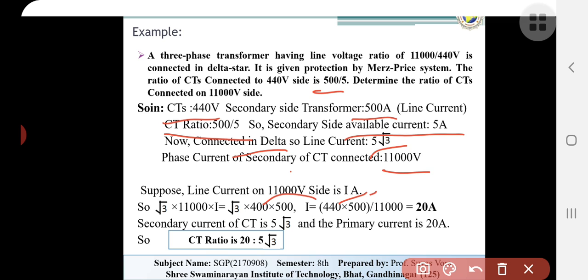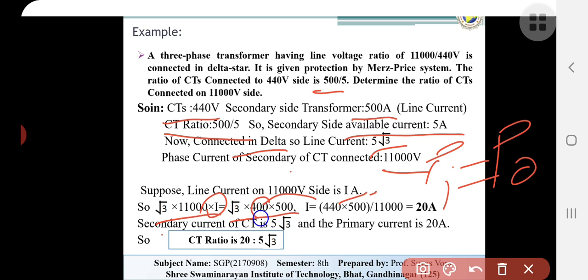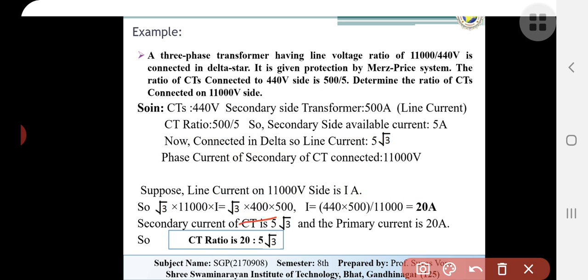So basically we equate the primary and secondary sides, because we know that the input power is equal to the output power. So here you can see √3 VI. Here V is 11,000 and I we can find from √3 × 440 × 500. Sorry, there is an error here, it should be 440, my mistake. So I is equal to 440 × 500 divided by 11,000, so 20 amperes. So we can see that the secondary side CT current is 5√3 and the primary current is 20 amperes.